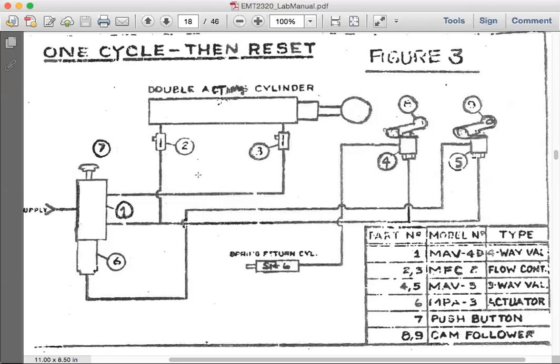Okay, so our initial stage is very simple, and since we have only one activation button, which is a push button, or stem number 7, let's see what we will do. When you press down the stem, so the stem is right now at the bottom, the pressure is being switched from the top to the bottom. All the pressure that was previously coming through the top now opens the venting path through the venting hole at the top of the left side of the MAV4D.